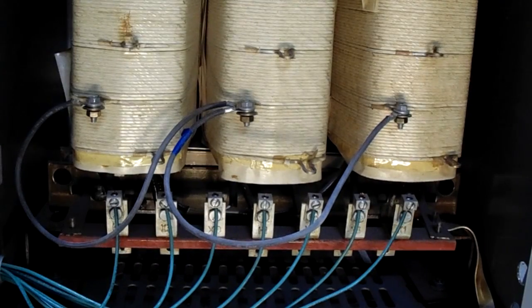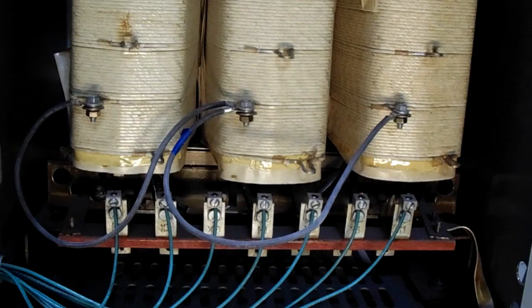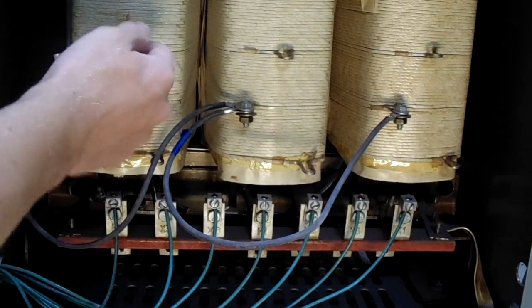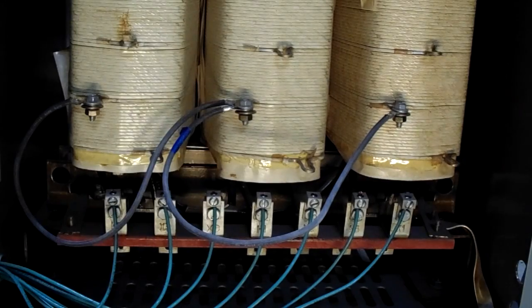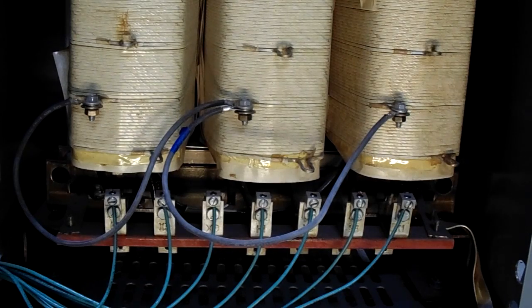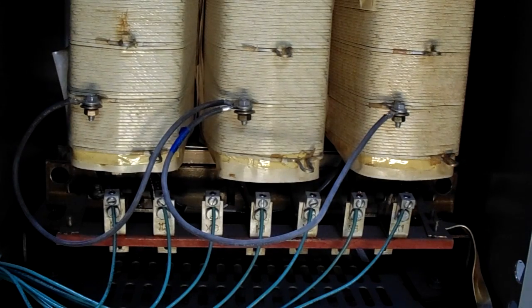And yeah, if you're going to use it in single phase, do remember that these windings are not normally meant to handle single phase current. So if this is a 13.8 amp transformer at 3-phase, then you're going to want to derate that.